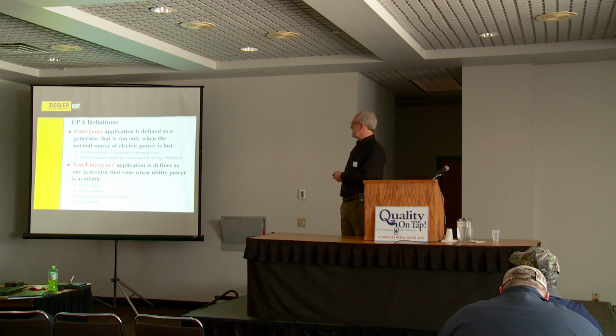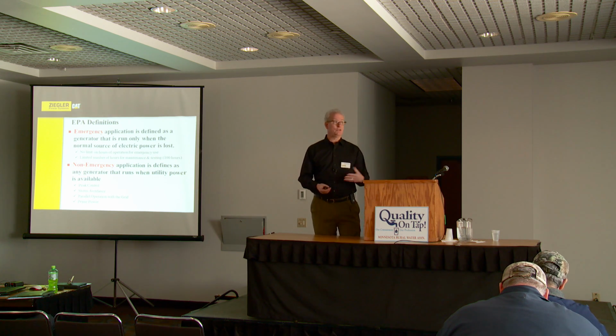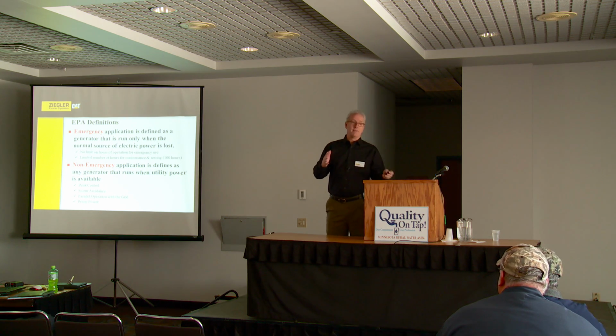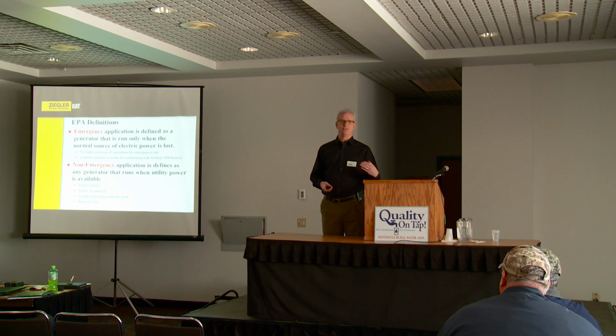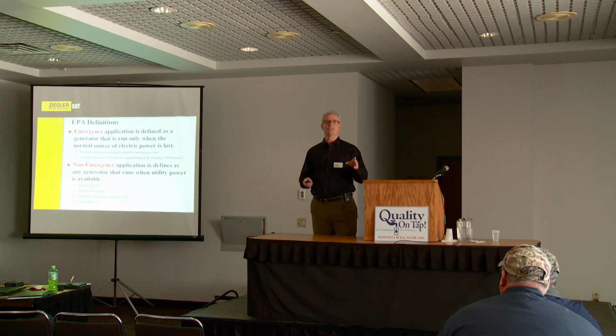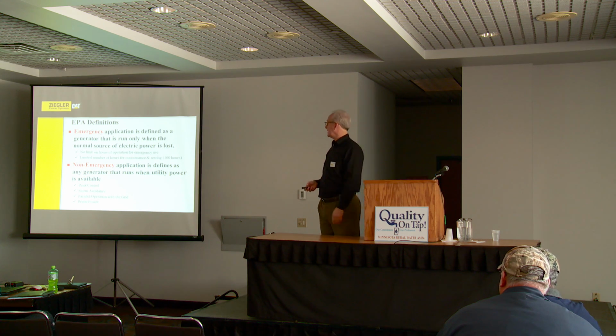So the way the EPA defines it, there are no limits on the hours of operation for emergency use. Then they also know there are times you need to test your emergency engines so that they'll work right. So EPA says you can run your emergency engine for up to 100 hours a year to do testing, according to the manufacturer's requirements or your association rules. I think of hospitals, where they have specific rules about testing their emergency generators. So EPA said that's cool. An emergency engine only runs when the power goes out. When power comes back on, it stops running, and it also runs to do testing. That's kind of what it's got.